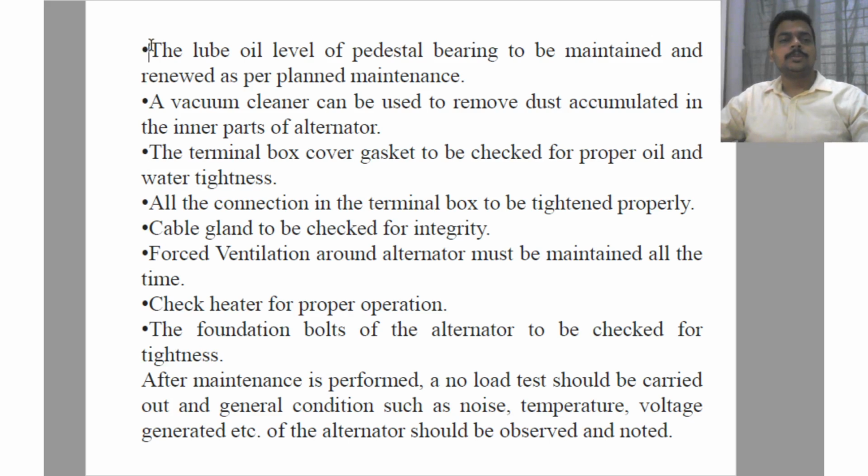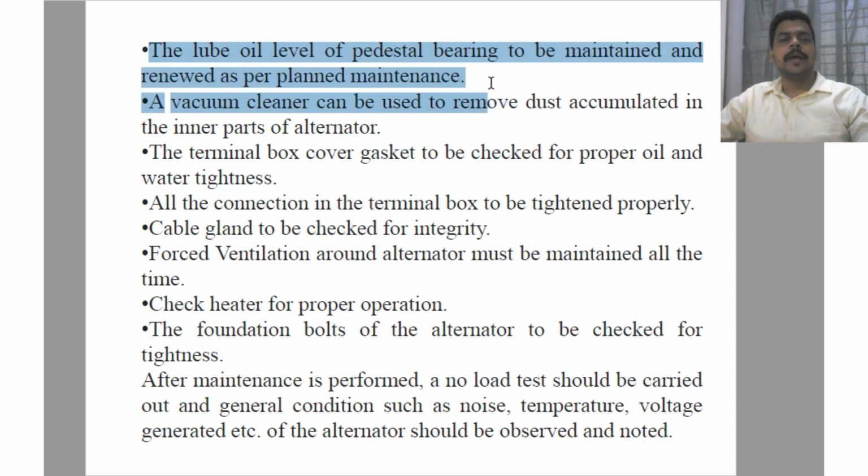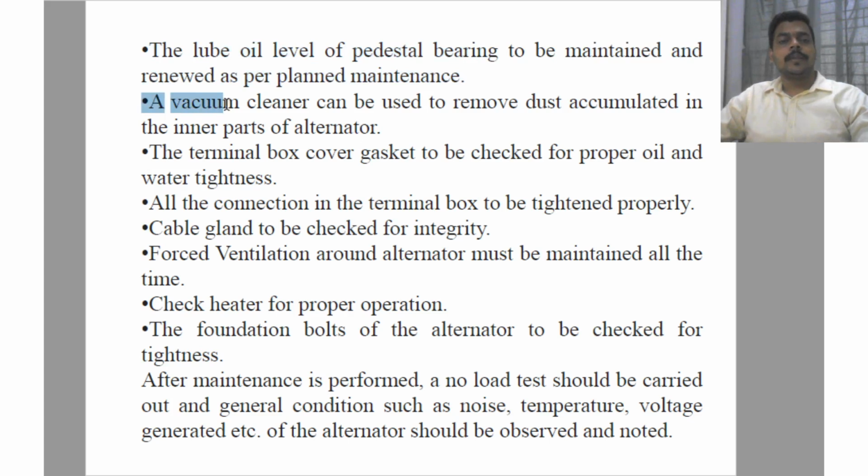Then we have to make sure that the lube oil level of the pedestal bearing is maintained and renewed as per the planned maintenance. If we are thinking of doing planned maintenance, then we have to take care of this point. A vacuum cleaner can be used to remove the dust accumulated in the inner parts of the alternator, but make sure that the alternator is turned off or shut down.